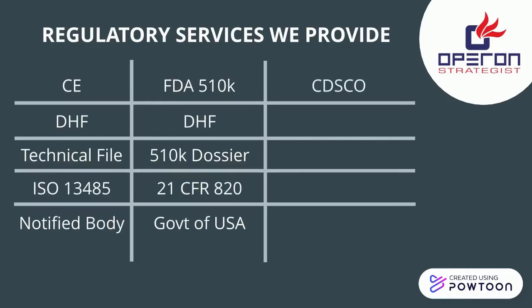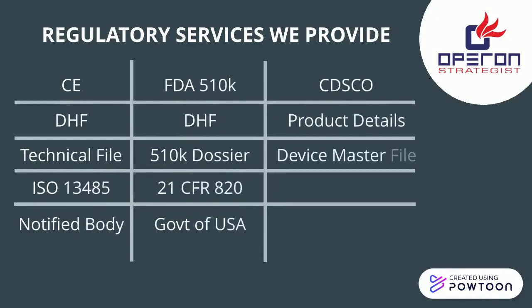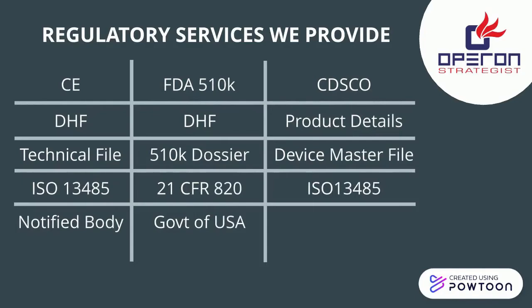CDSCO. To acquire CDSCO, also known as Indian FDA, the manufacturer. Product details. Product details must document the product quality, safety and performance under the Device Master File, DMF. There are two stages for this license. One is test license and another is manufacturing license. ISO 13485. ISO 13485 certification is a mandatory requirement for quality management system. Government of India. Submission of all the files are done to the CDSCO via online portal, who then audits the complete applications and also audits the facility. Only upon complete assessment the license is issued.